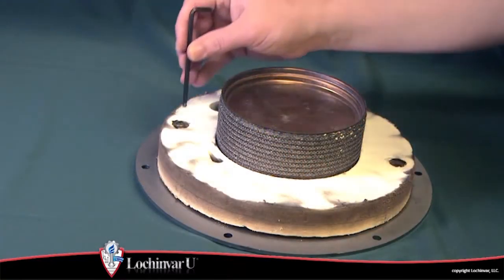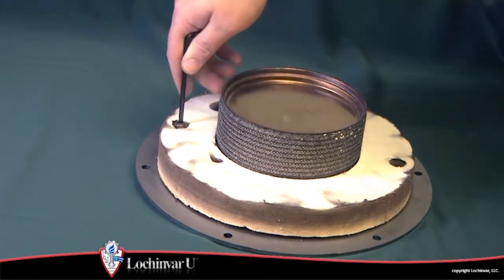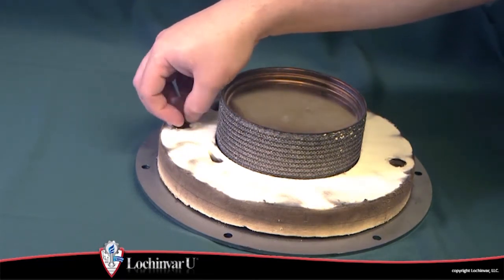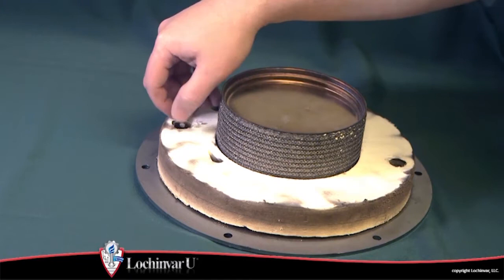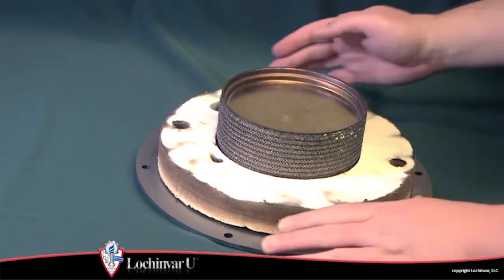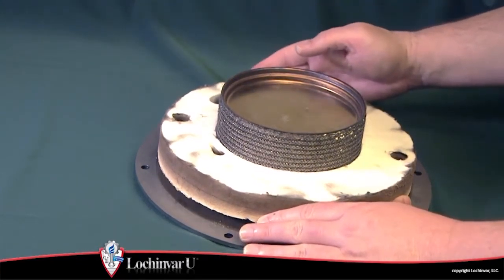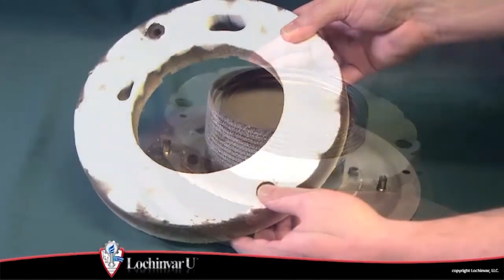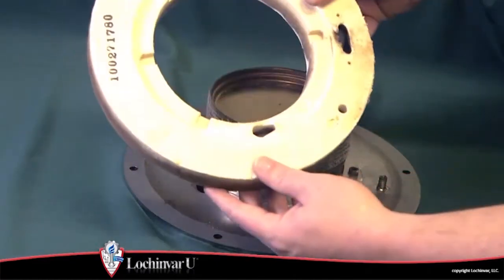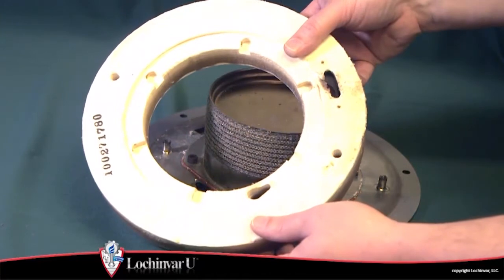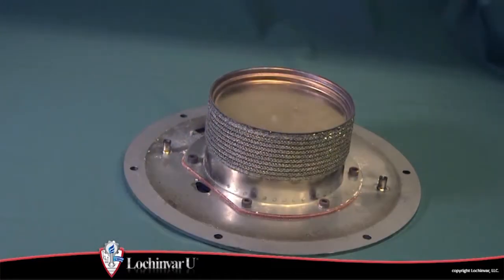Using a 5mm Allen wrench, remove the 2 screws and washers that secure the insulating refractory material to the bottom of the heat exchanger top plate, and carefully remove the insulating refractory from the heat exchanger top plate. Inspect the insulating refractory for damage. If the refractory is damaged, it must be replaced.